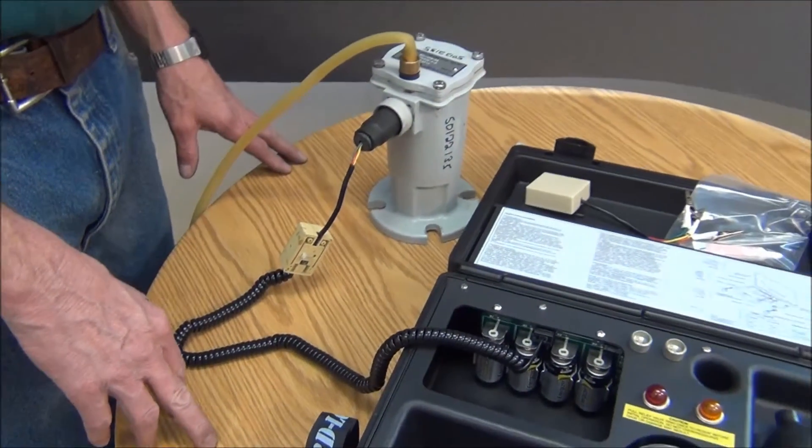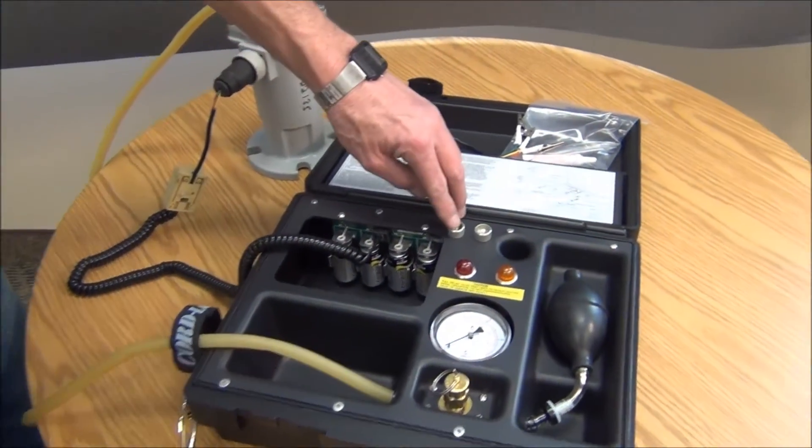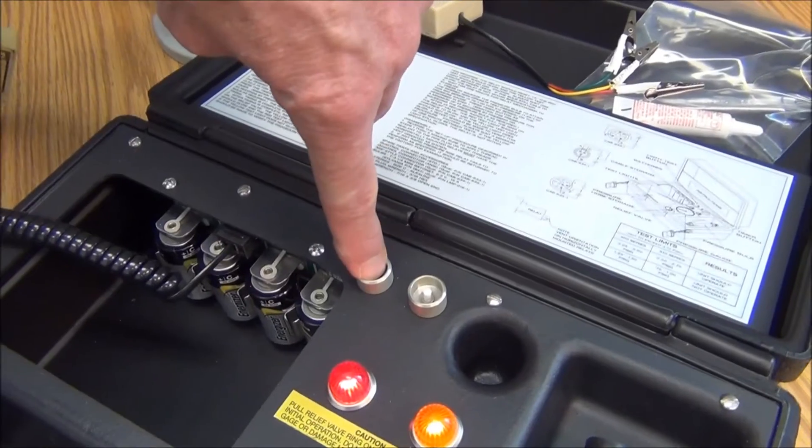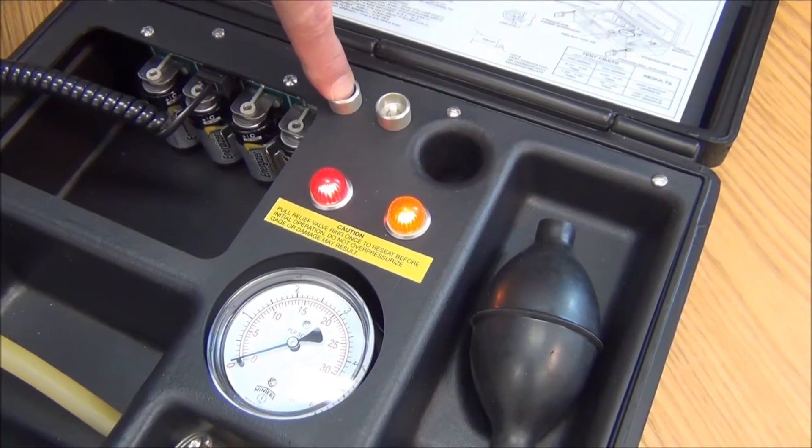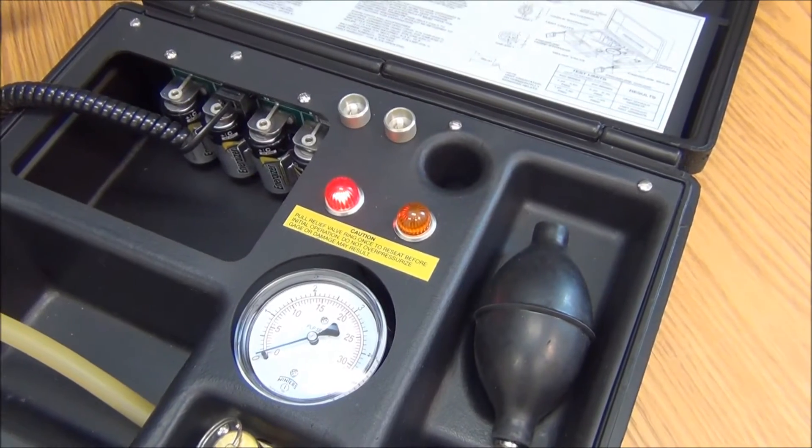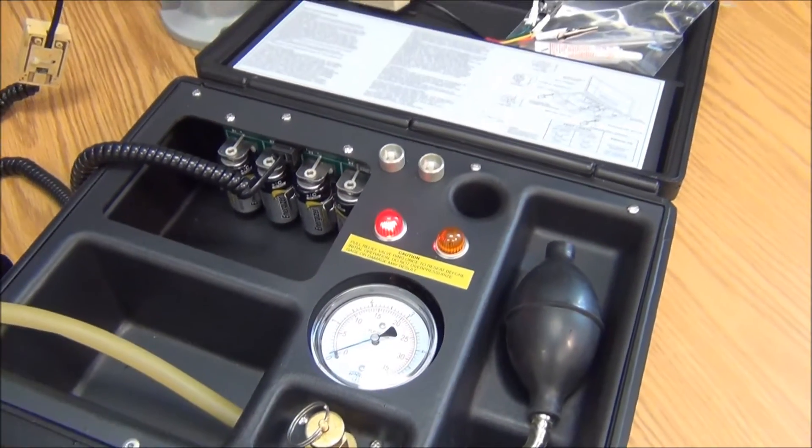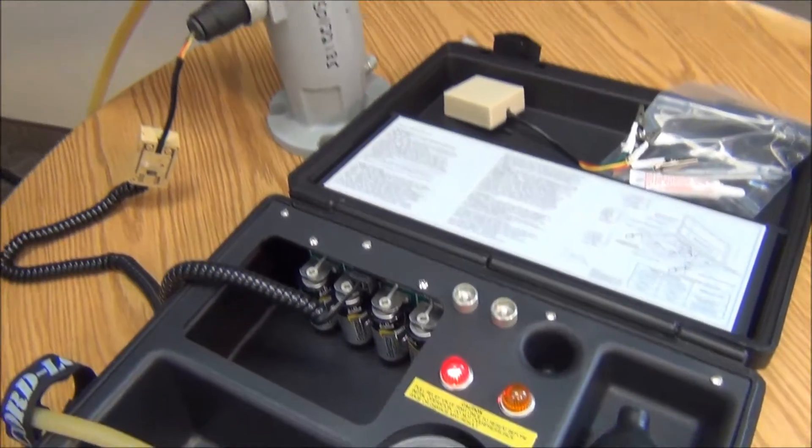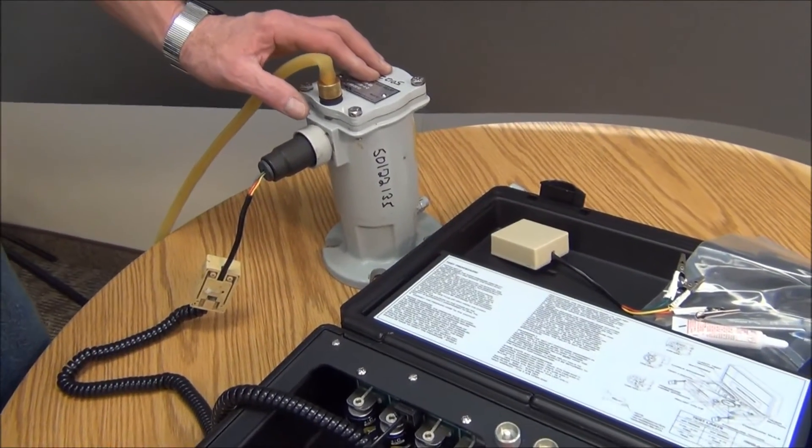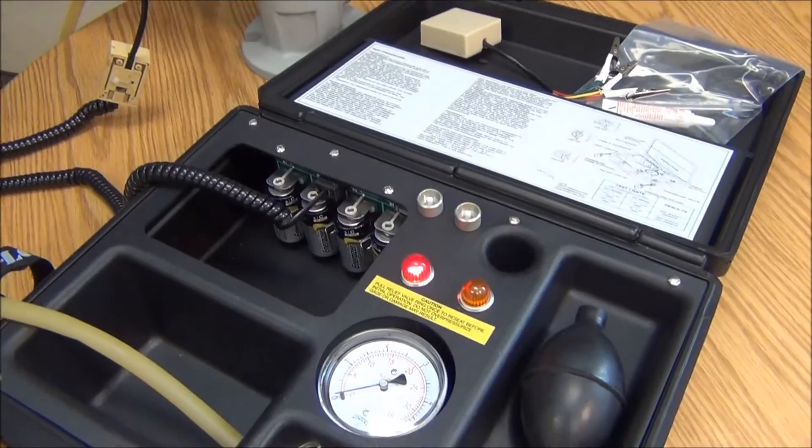As far as using the unit, the first thing you do is push this left-hand button. When you hold it down, you should see two lights, which turns the power on to this test kit. After you take your finger off the button, you should see a red light. That means this unit is in the untripped position.